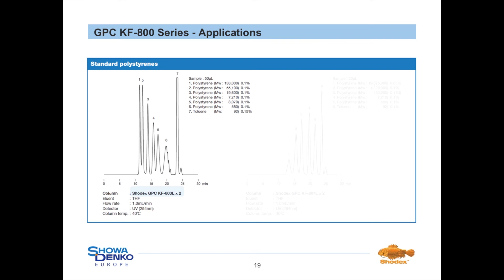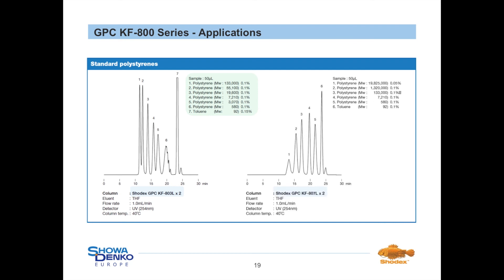The performance of the KF-800 columns is shown in this slide. Different polystyrene standards were tested over a wide molecular weight range. On the left side, a combination of two 803L columns leads to good separation of polystyrenes from 92 up to 133,000 Dalton with high resolution. On the right side, two 807L columns were combined to separate a polystyrene mixture between 92 and 19,825,000 Dalton — a nice separation with high resolution was obtained, confirming the good performance of mixed-gel columns over a broad range.